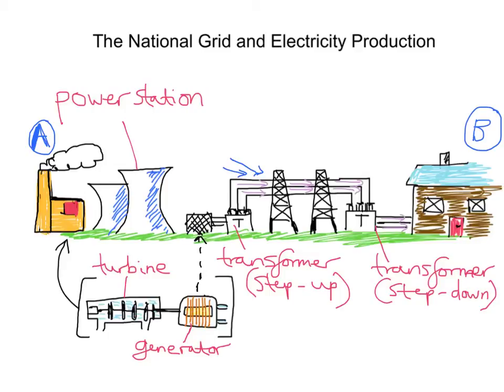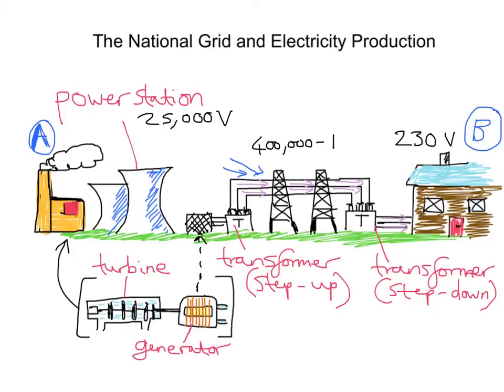The voltage of household electricity is about 230 volts. Power stations produce electricity at 25,000 volts — already a big difference. But electricity is sent through the national grid cables at its peak at 400,000 volts, then 275,000 volts, and even 132,000 volts. We're basically bringing down that voltage as we get closer to where we deliver the electricity — from 400,000 to 132,000 volts through the national grid.